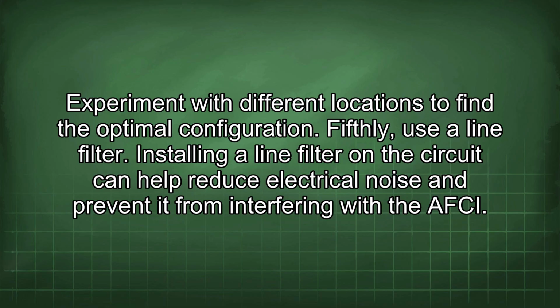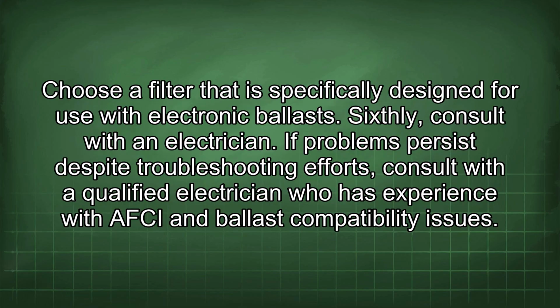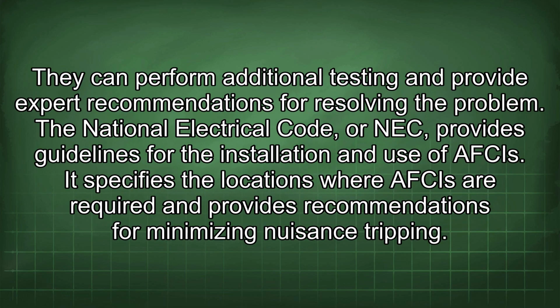Fifthly, use a line filter. Installing a line filter on the circuit can help reduce electrical noise and prevent it from interfering with the AFCI. Choose a filter that is specifically designed for use with electronic ballasts. Sixthly, consult with an electrician. If problems persist despite troubleshooting efforts, consult with a qualified electrician who has experience with AFCI and ballast compatibility issues. They can perform additional testing and provide expert recommendations for resolving the problem.